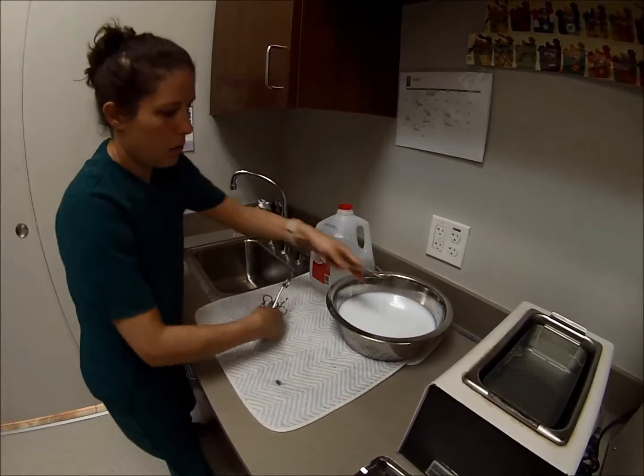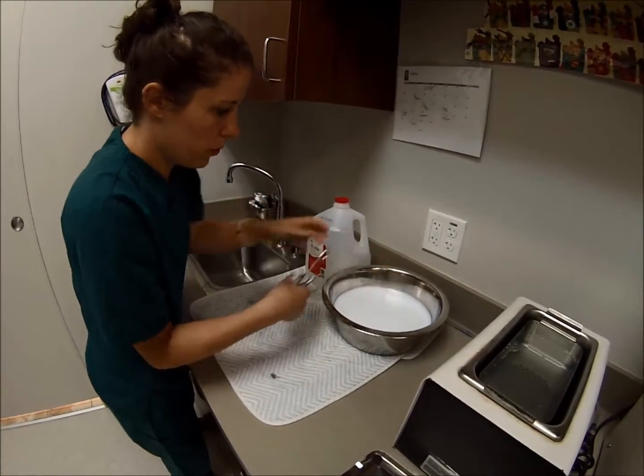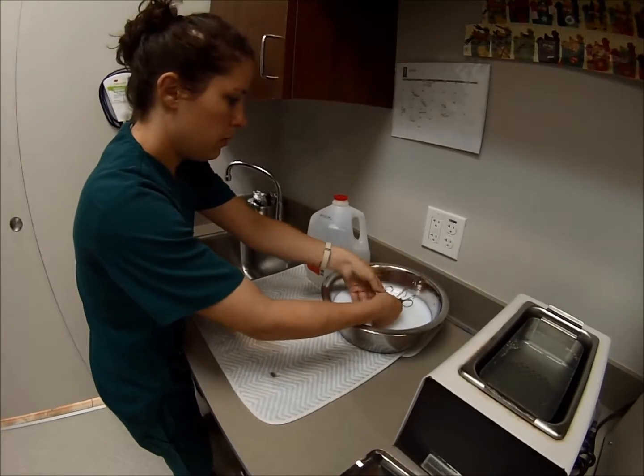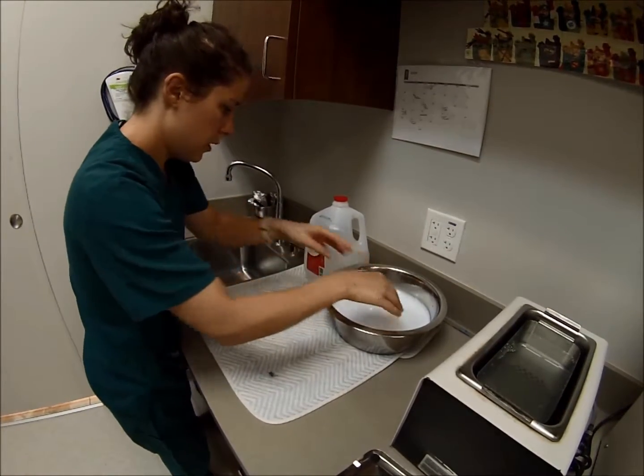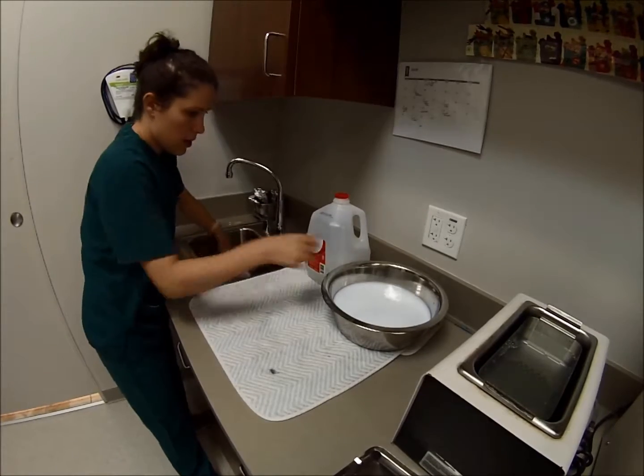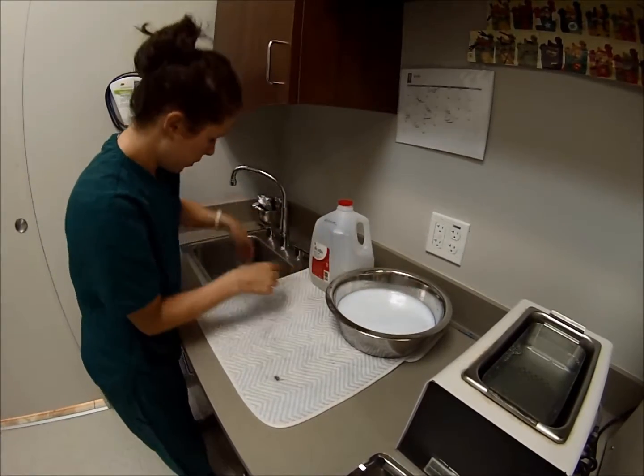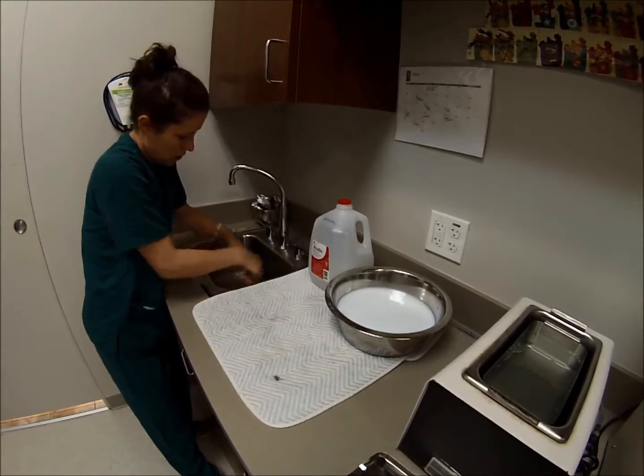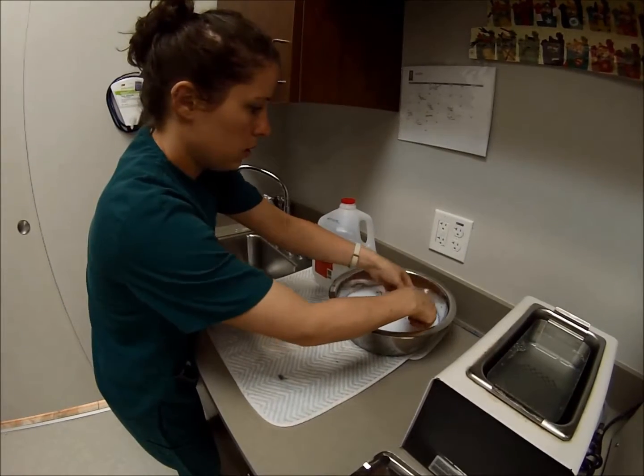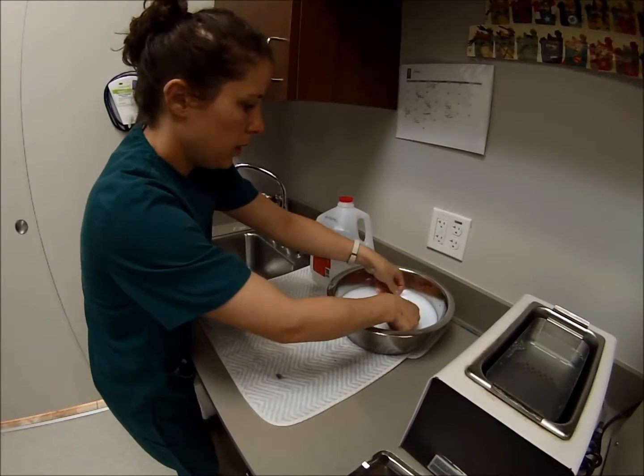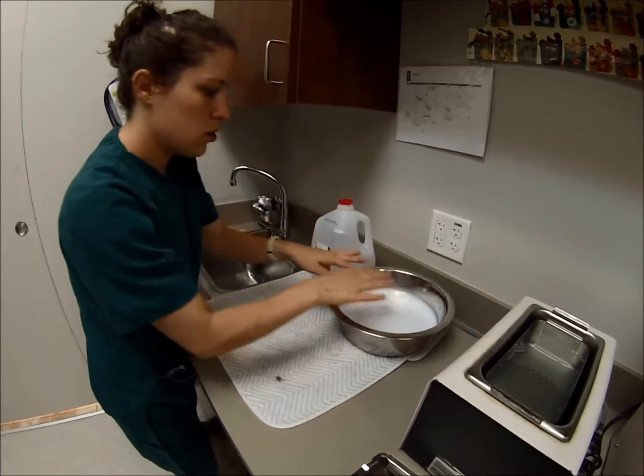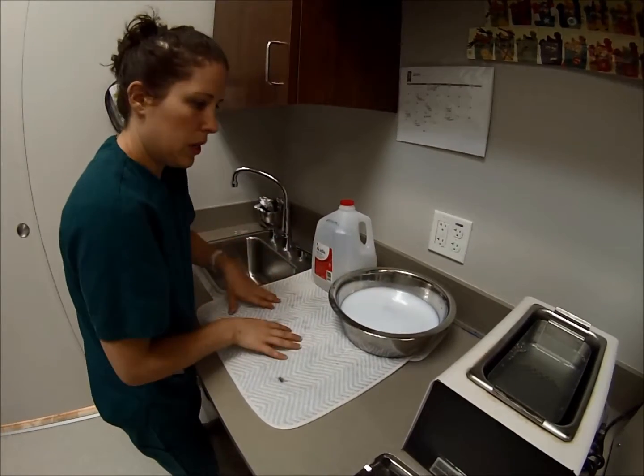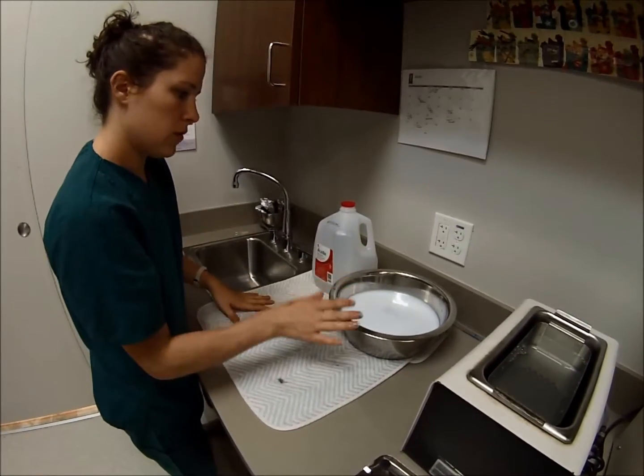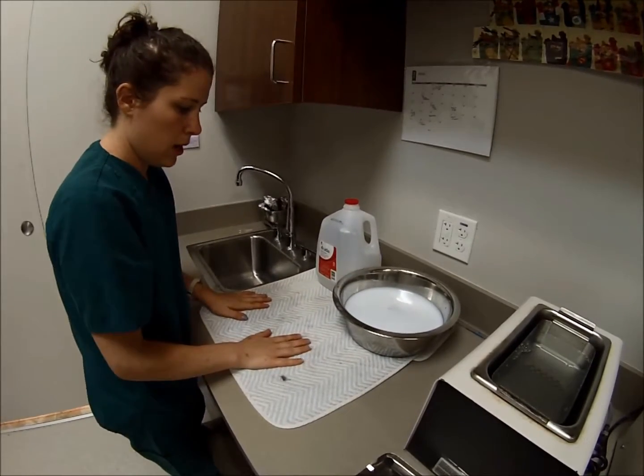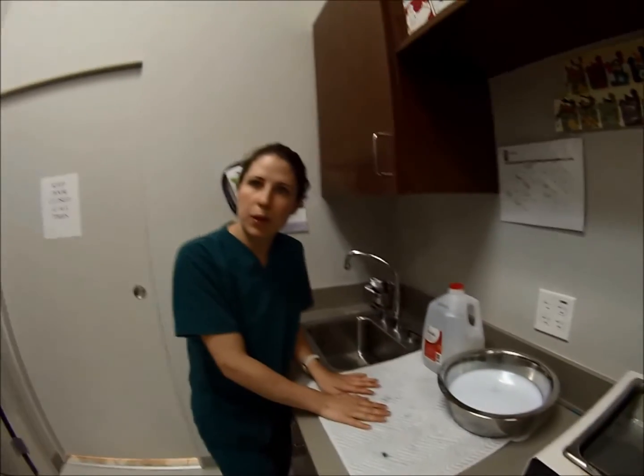Same deal, I want to make sure that my instruments are open when I'm loading them in. The lubricant bath just prevents any rust from building onto the instruments and prevents corrosion, so this is an important step. We typically let these soak for 5 to 8 minutes. Once it's finished, we'll lay them out to dry. And once they're dry, we can go ahead and wrap them up in a pack.